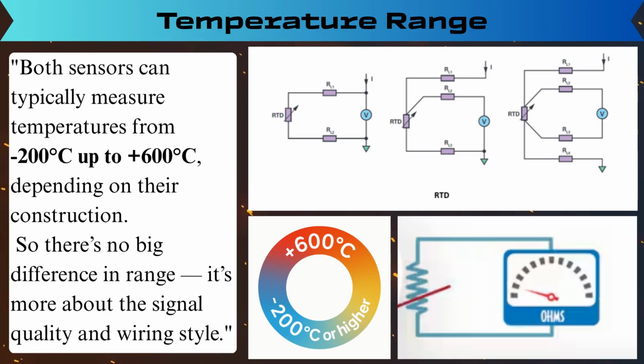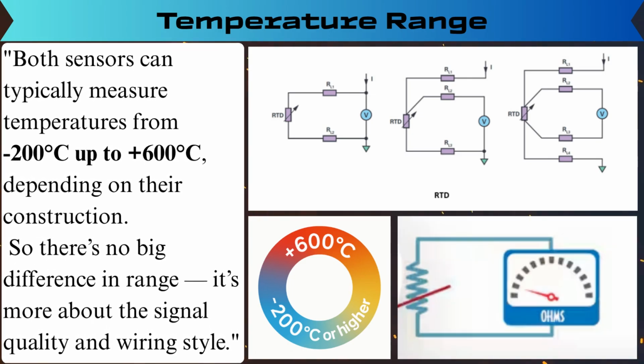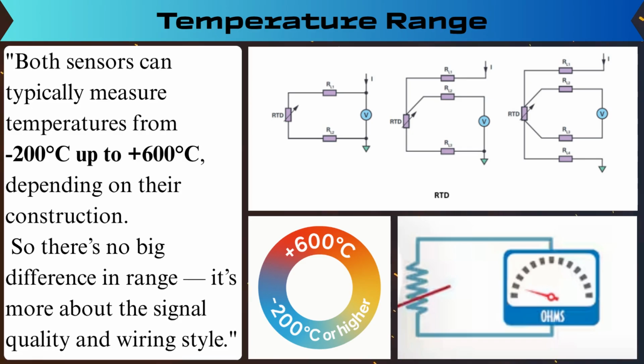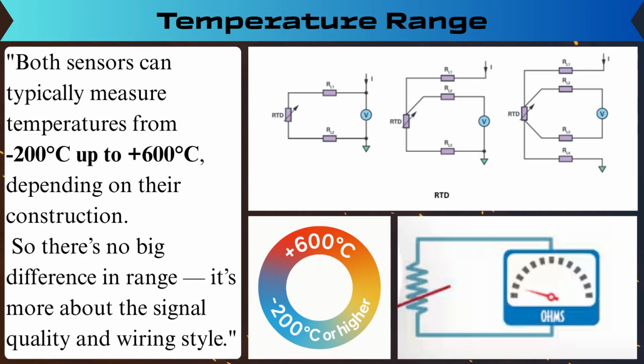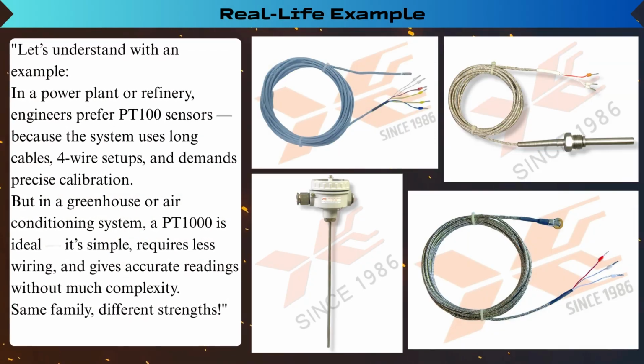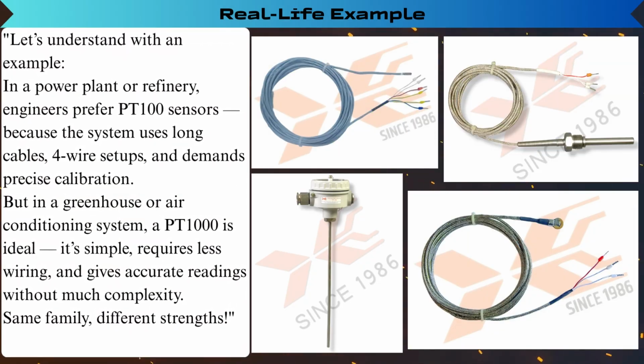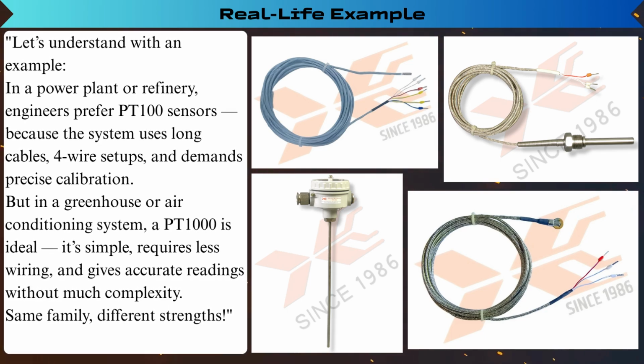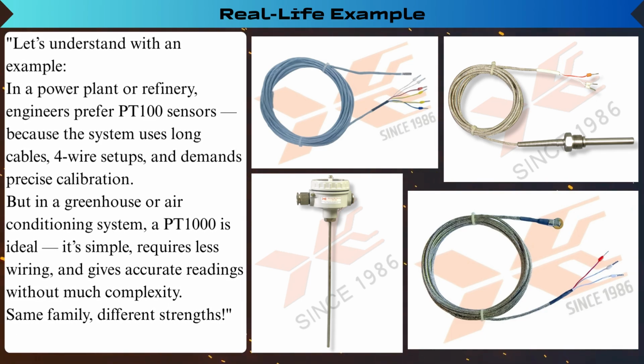Temperature range. Both sensors can typically measure temperatures from -200 degrees Celsius up to +600 degrees Celsius, depending on their construction. So there's no big difference in range, it's more about the signal quality and wiring style. Real-life example. Let's understand with an example. In a power plant or refinery, engineers prefer PT100 sensors because the system uses long cables, 4-wire setups, and demands precise calibration. But in a greenhouse or air conditioning system, a PT1000 is ideal. It's simple, requires less wiring, and gives accurate readings without much complexity.